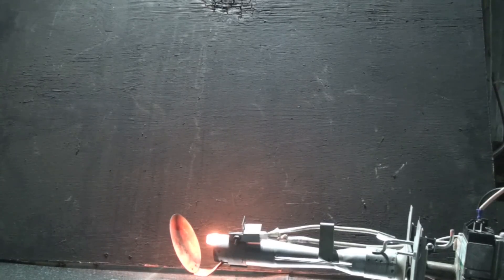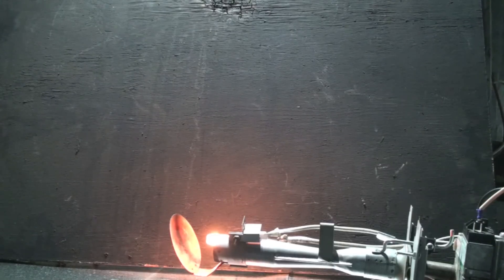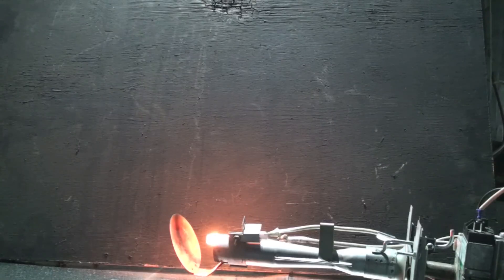Okay, you can see the hot surface igniter's come on. This is one of the long heating hot surface igniters. It takes between 30 and 45 seconds, I can't remember which, for it to light off.